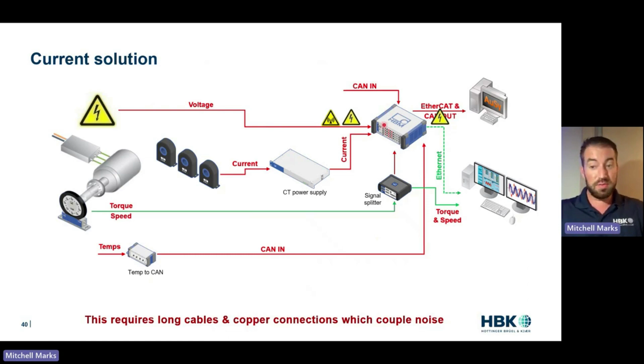So what could be better? What if we had a box that did all the digitization sitting right next to the machine? What if we had high voltage modules that were completely floating, sitting next to the machine, digitizing, and then connected to the measurement equipment over a fiber optic cable? What if the current sensors plugged into that completely isolated box, got digitized, and sent back over fiber optic cable? This is the future we're looking at.